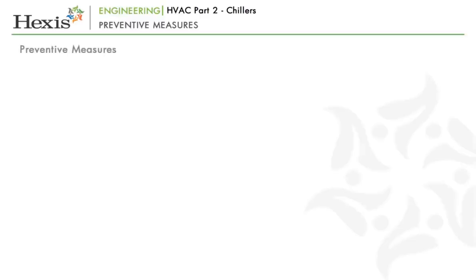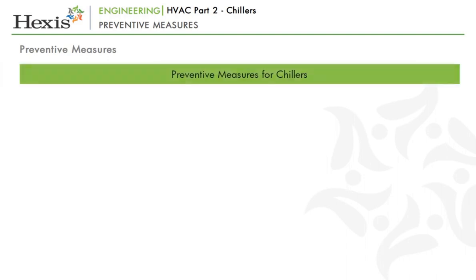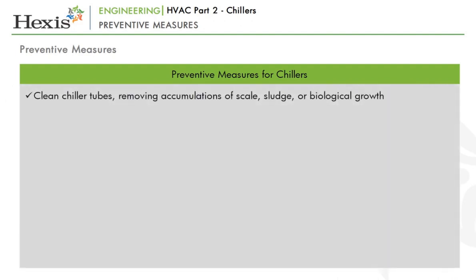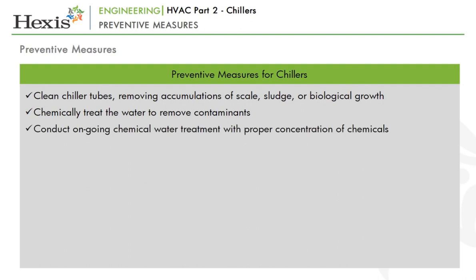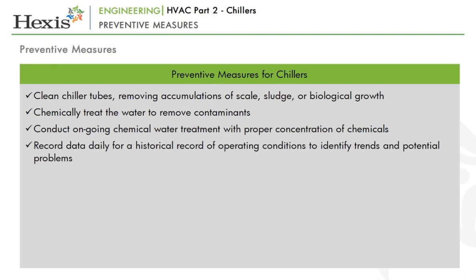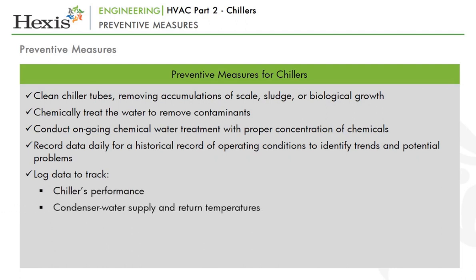Next, we will look at preventive measures for smooth functioning of chillers. Preventive measures include: cleaning chiller tubes to remove accumulations of scale, sludge or biological growth; chemically treating the water to remove contaminants and prevent accumulation on heat transfer surfaces; conducting ongoing chemical water treatment with proper concentration of chemicals; and recording data daily for a historical record of operating conditions to identify trends and potential problems. Data to track includes chiller performance, condenser water supply and return temperatures, evaporator and condenser pressures, oil temperatures and pressure, and drive motor current and voltage.